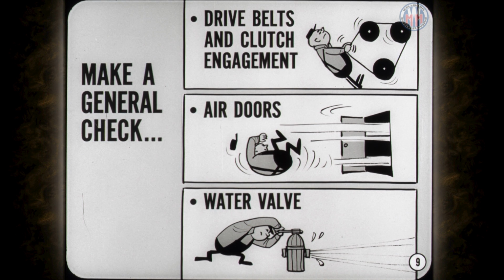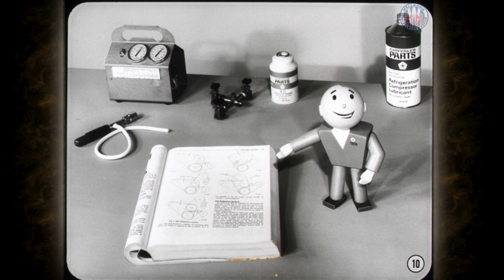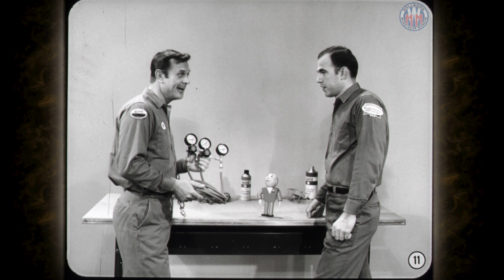Okay, I'll buy that, but how about testing? Where do you start? First, you make a general check for things like broken or loose drive belts, clutch engagement, air doors not operating properly, or a water flow valve that doesn't shut off. Then you start in on the refrigeration part of the system. And don't just guess at belt tension. Use the checking methods given in your service manuals to make sure. Slipping belts can really cut down the cooling output. Hiya, Tech. Thanks for the reminder.